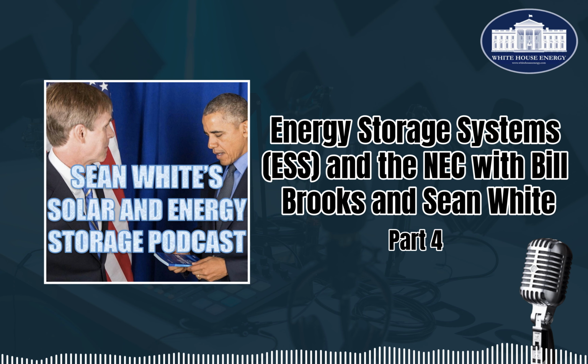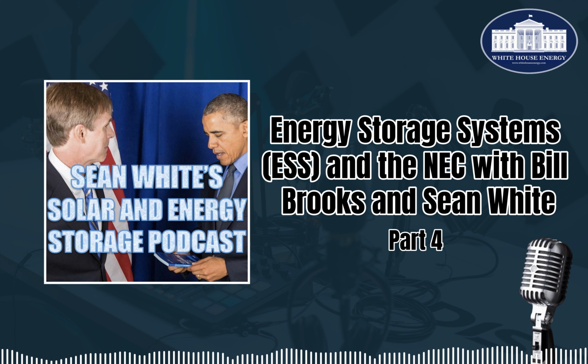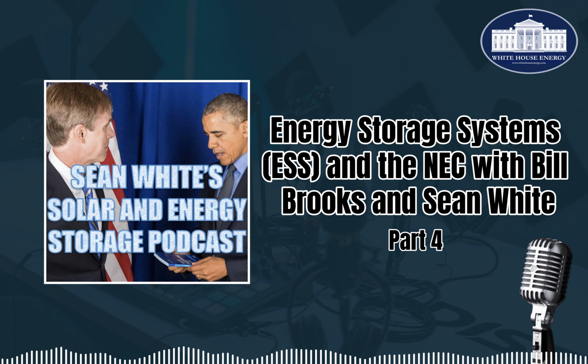Yeah, there's not a tremendous amount of difference between the 2017 code, which you're currently on, and the 2020 code. Let's say you have a 100 amp service and you wanted to put a 100 amp PV system on the supply side. According to the 2017 code, the breaker rating is going to be 100 amps, which means it's going to have a continuous output of 80 amps. That's going to be well within the rating of the service conductors and the service equipment, because the rating of the service is 100 amps.